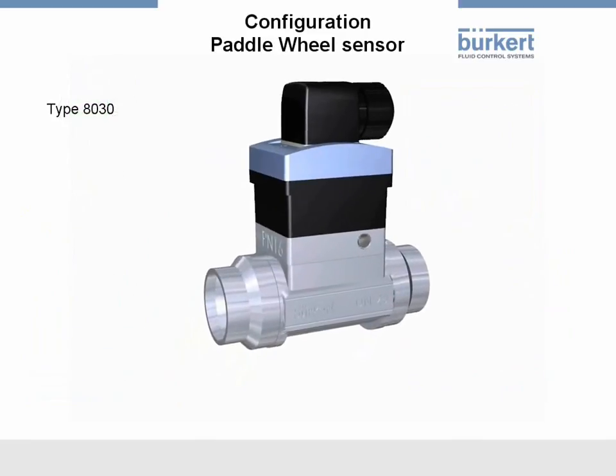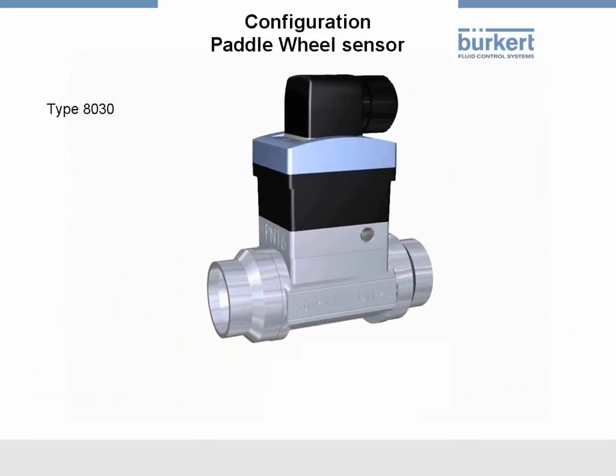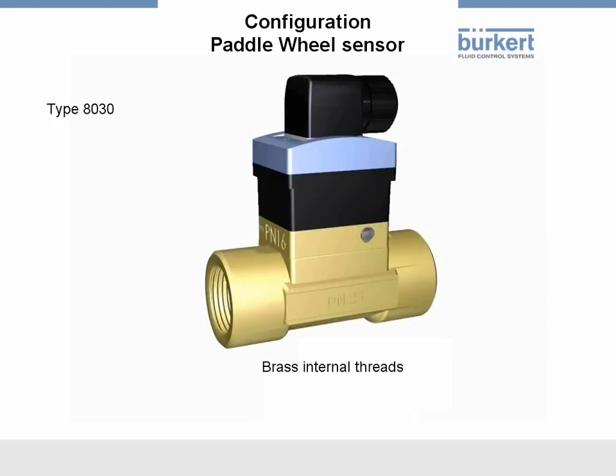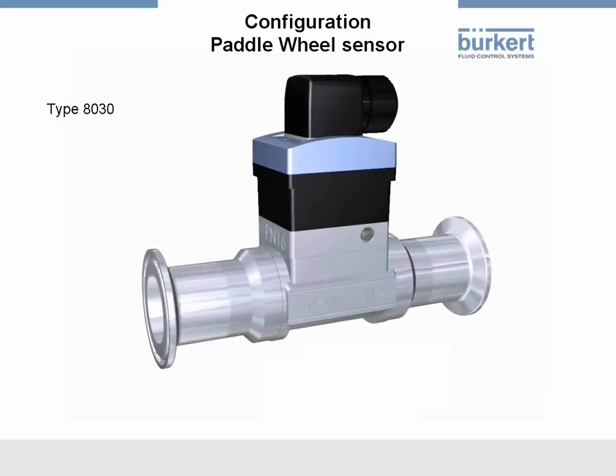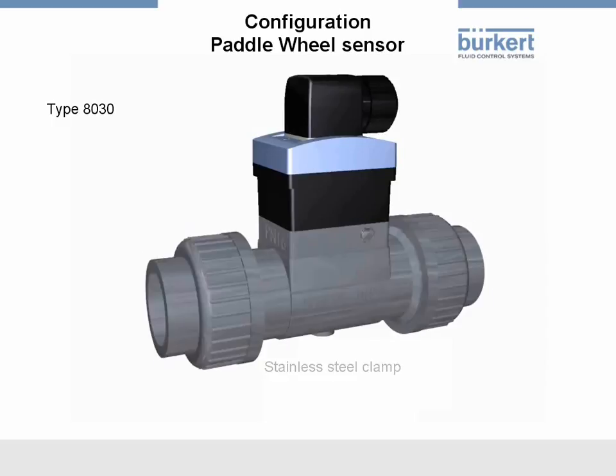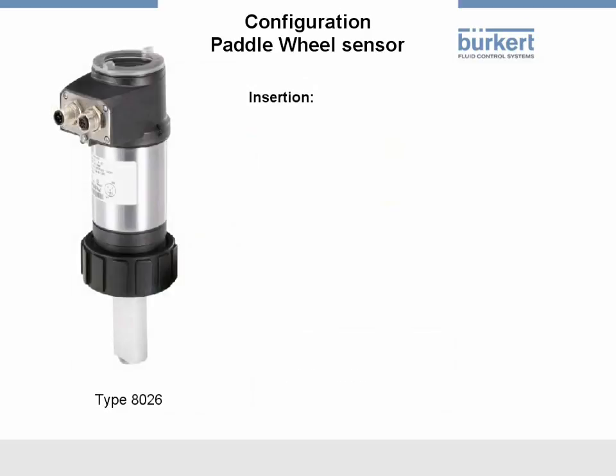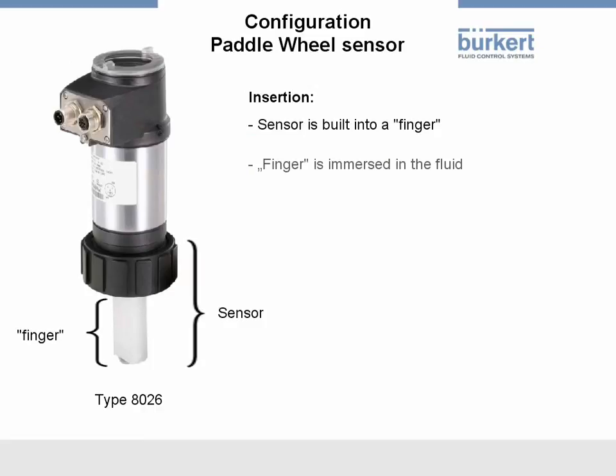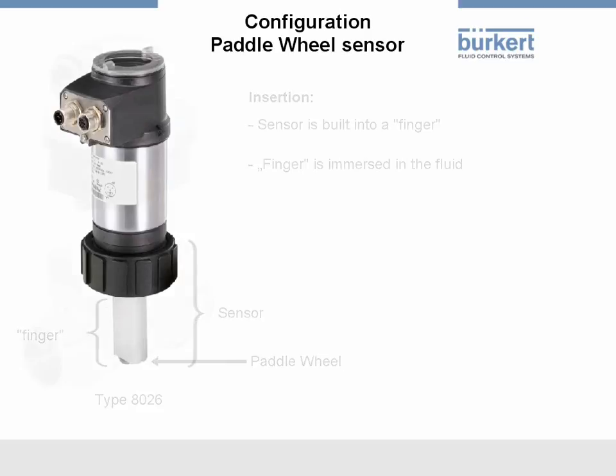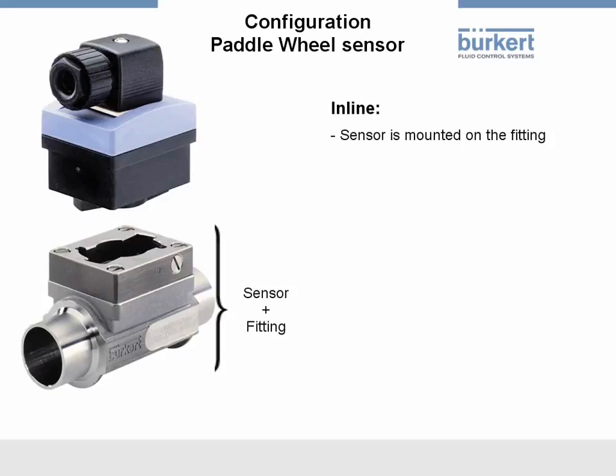We'll now show you a selection of different combinations of materials and process connections, such as stainless steel with welded connection, brass with internal threads, stainless steel with internal threads, stainless steel with a clamp, and PVC with external threads. Insertion means that the paddle, which is built into a finger, is immersed in the fluid to be measured. In the inline variant, the paddle is mounted directly on the fitting.